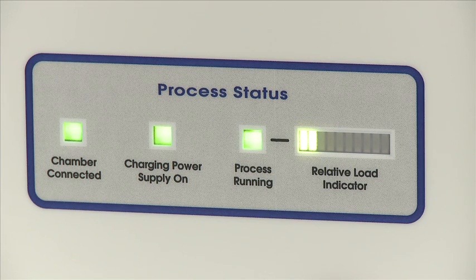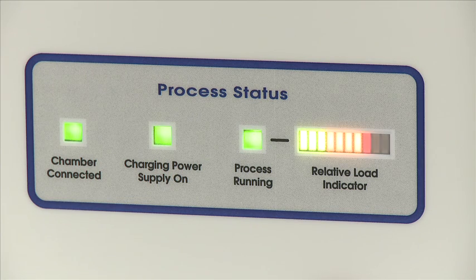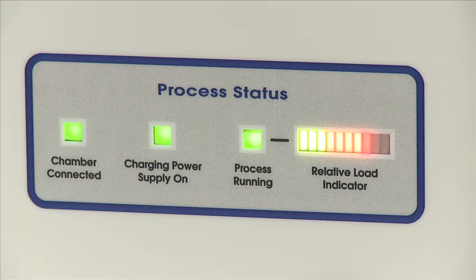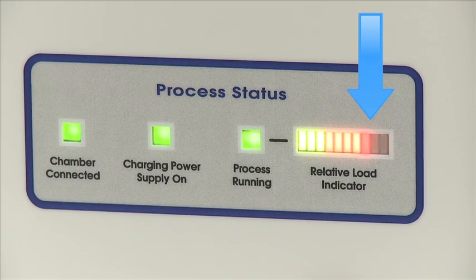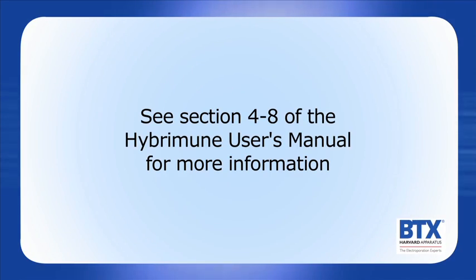On the relative load indicator, a few bars should light up green for about 15 seconds because the 40-volt sine wave is being applied. It will increase in bars because of the 70-volt sine wave for about 20 seconds. During the entire run, it is normal to see the bars increase and decrease. It is not typical to see the bars go into the red. If this occurs, it is because there are too many ions present in the sample. See Section 4-8 of the Hybrimune user's manual for more information.